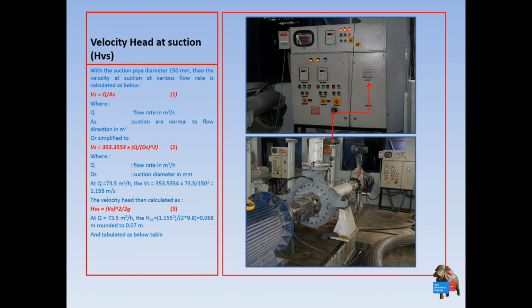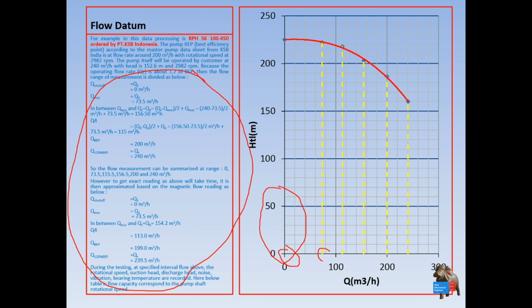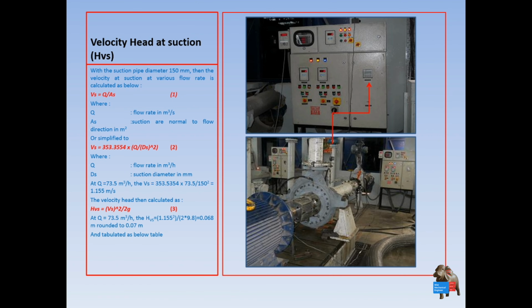As I mentioned before, you record the velocity head at the suction by transferring the flow capacity at each point. At shut-off it is of course 0, but at the next test, this point and this point, this point and this point, you have to record the pressure at discharge, and the RPM. You also have to record the power into the motor, and you move to the next flow capacity, and the next, and the next. In this figure you see I have a pump here. This is a motor.